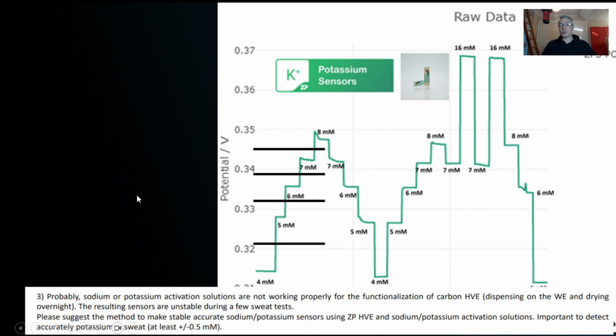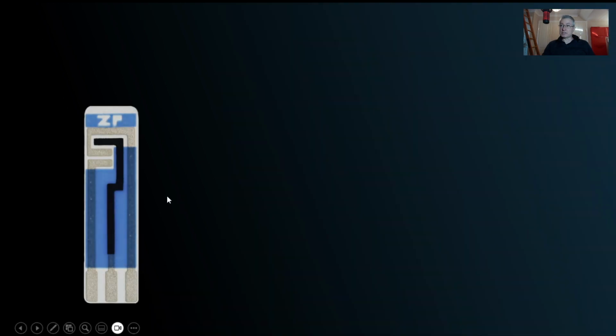So I think your concern is actually that your testing leads to an offset variability. That offset variability means you think you've got poor resolution. The poor resolution makes you think then you have poor accuracy, but it's really just the way the sensor's being tested. So you put a solution on there, you get a signal equals a value plus an offset.